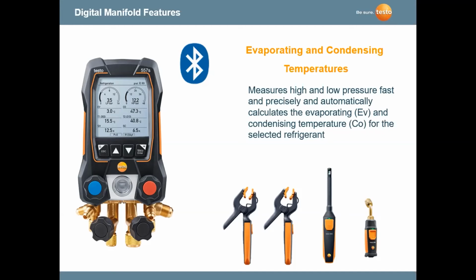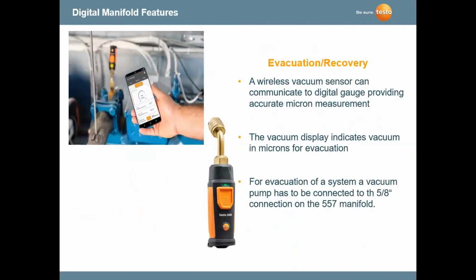All these wireless probes are communicating to the instrument. From the instrument, it's going into your app. If you shut your instrument off, which is the 557, those probes will then be redirected to the app. So you can use these with an app, or you can use them with the instrument, which eventually communicates to the app. A lot of versatility in these instruments.